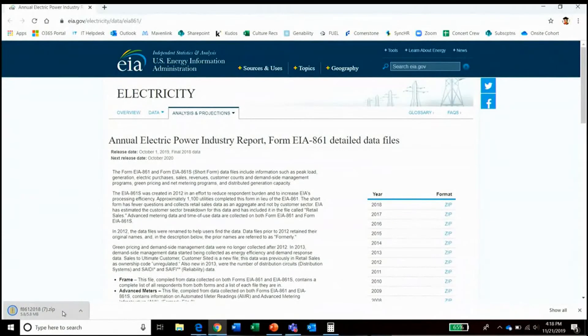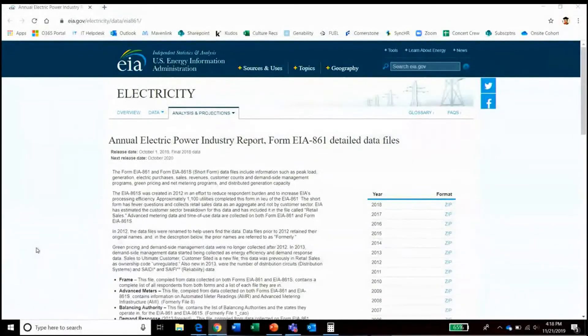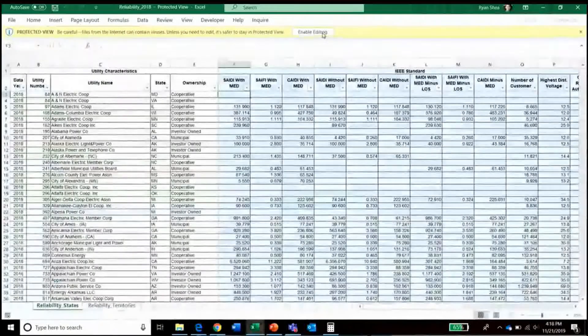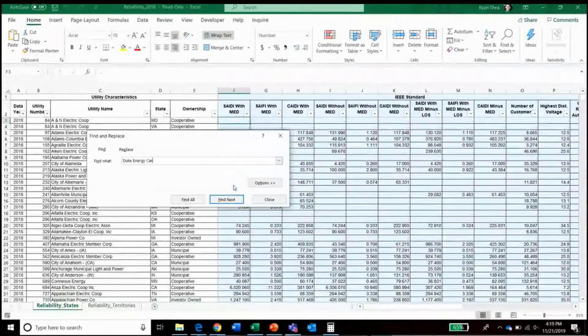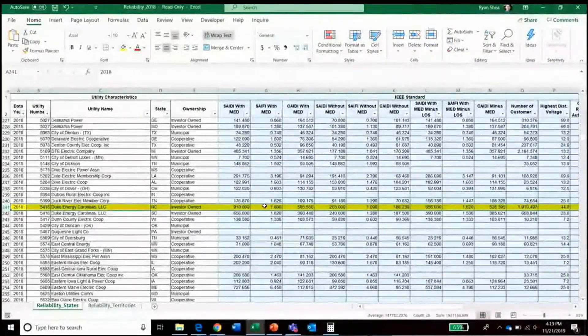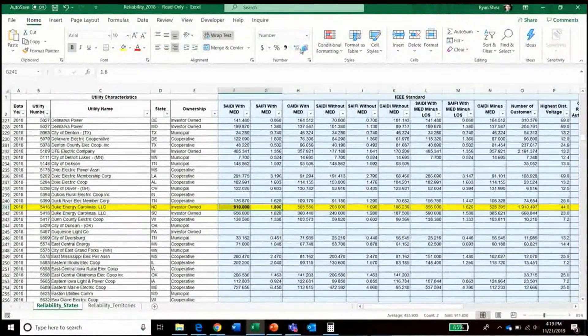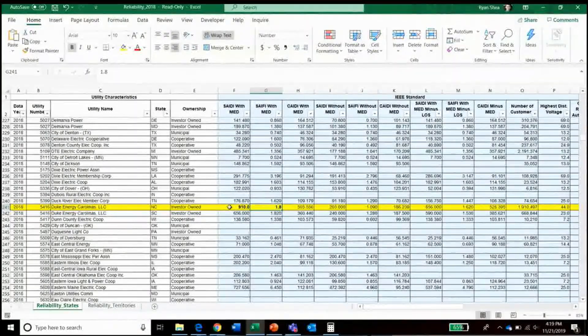Next we'll click on the second link listed, which takes us to EIA's site, where on the right we can download 2018 data that EIA tracks. If we click on 'Reliability 2018,' we can see the grid outages that have occurred for each utility. For Charlotte, we can find the associated utility Duke Energy Carolinas, and see that they experienced around 1.8 outages last year that lasted around 910 minutes each.